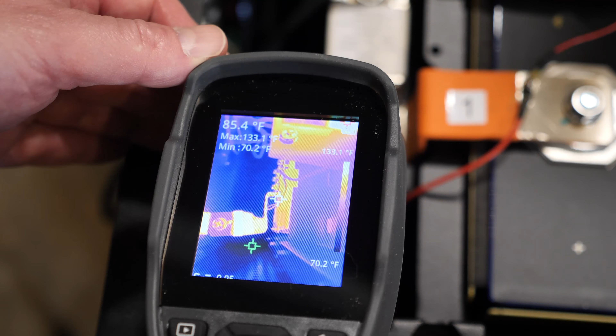We're showing 130 degrees. All right, now I'm looking down below if I can get it on there. That's the negative terminal. We're showing 110, 111 degrees on the bus bar down there. Anything else that goes right to the BMS is probably not accurate, but we're showing 89, 90 degrees.